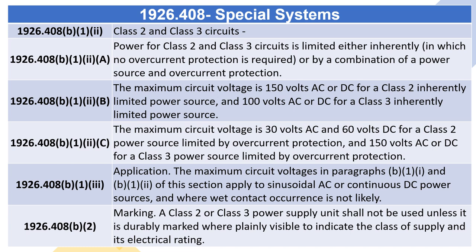1926.408(B)(1)(ii) — Class II and Class III Circuits. (A) Power for Class II and Class III circuits is limited either inherently, in which no overcurrent protection is required, or by a combination of a power source and overcurrent protection. (B) The maximum circuit voltage is 150 volts AC or DC for a Class II inherently limited power source, and 100 volts AC or DC for a Class III inherently limited power source. (C) The maximum circuit voltage is 30 volts AC and 60 volts DC for a Class II power source limited by overcurrent protection, and 150 volts AC or DC for a Class III power source limited by overcurrent protection.